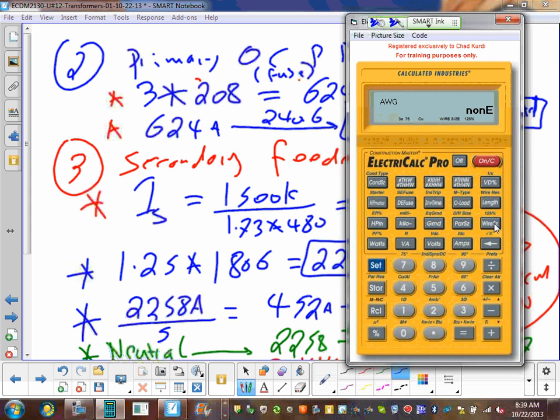It tells you there is no size that can carry this. Why did I put set? If you put set, wire size is sized based on 125%. Can you guys see that? Okay, now I'm going to go parallel. Then hit 5 and parallel. And what did we come up with? 500 kcm. What was my size before? Was it 700?